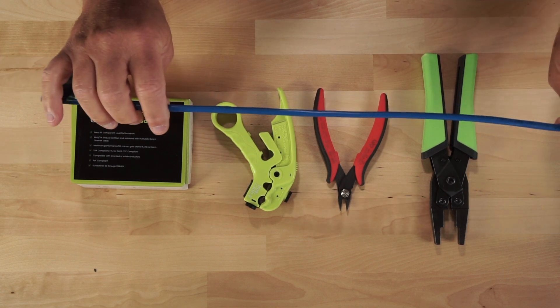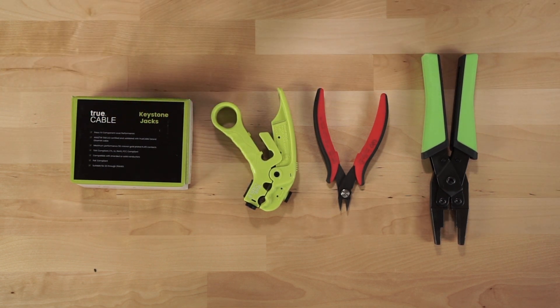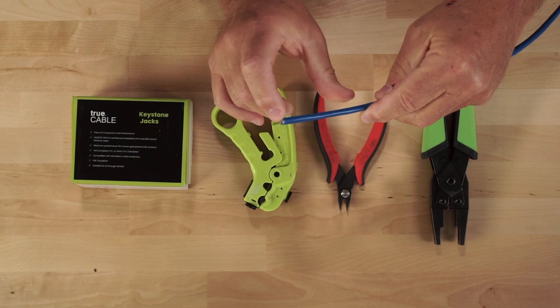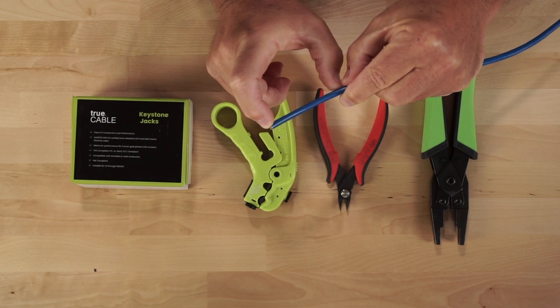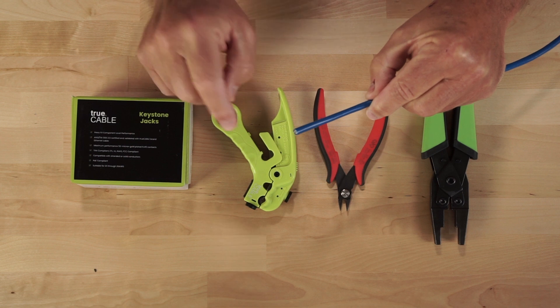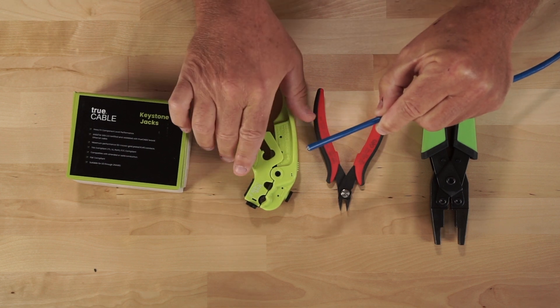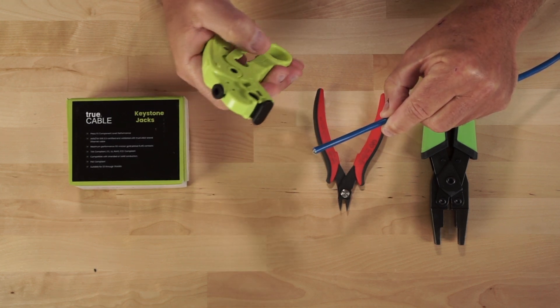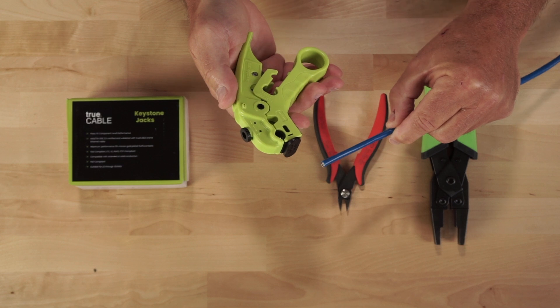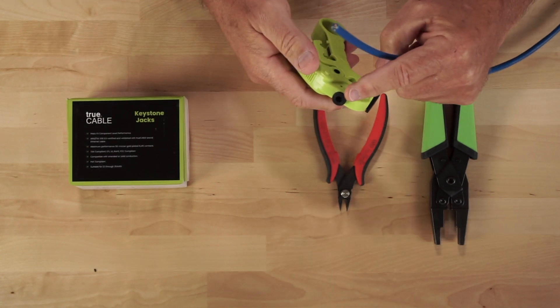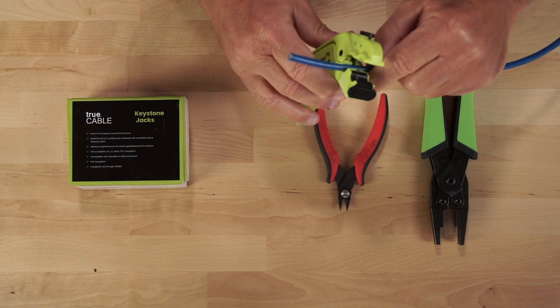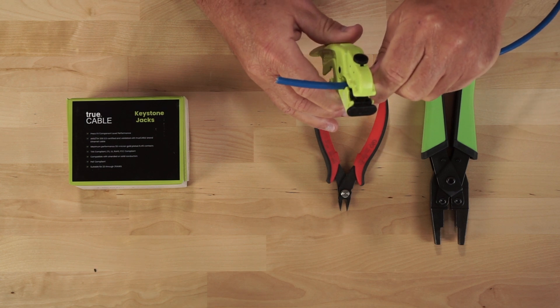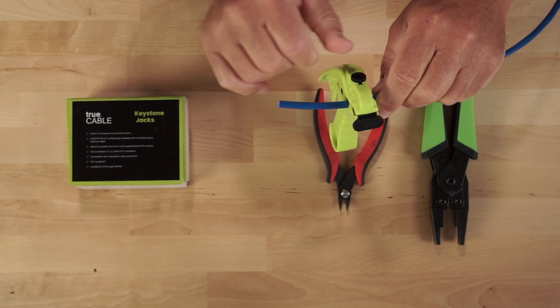So first thing we're going to do is we're going to cut our cable and I'm going to cut off about two and a half inches. Well, not the whole cable, but we're going to take the jacket off and you have to be really careful not to damage or remove the shield. So with the stripping tool, the blade has an adjustable knob at the top, so what you want to do is do a couple of practice cuts at first so you can get your blade adjusted.